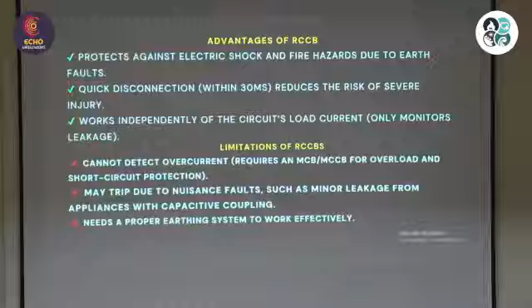Then the RCCB, what happens? It can monitor current differences, but it can't detect this since there's no difference between live and neutral. That's why we have to use MCBs. We normally use MCB for overload protection and short circuit protection.